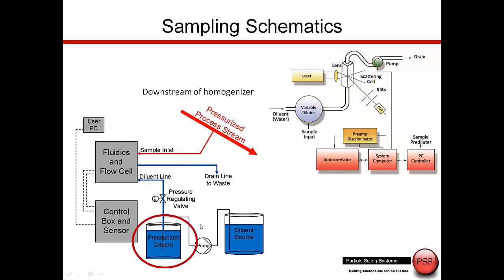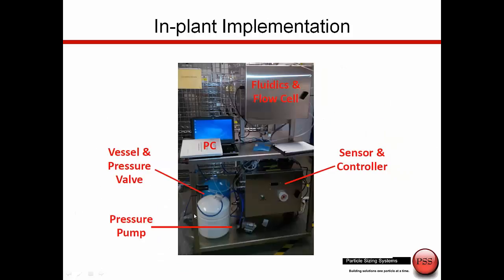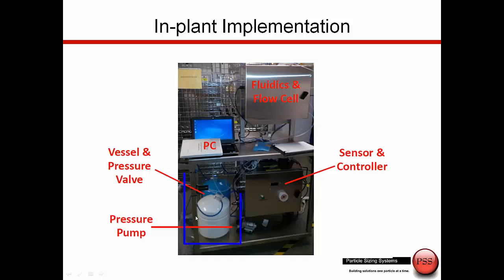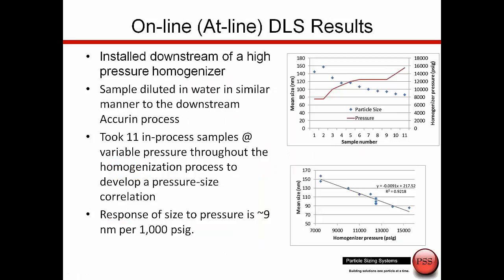The diluent source is pressurized to come into the fluidics, so we can perform DLS measurements in-process. Here is a picture of this instrument in the customer's processing plant. The fluidics is up here, this is where the sensor is, and the pressurized diluent is kept down here to pump into the system for dilution — all this downstream of the homogenizer.